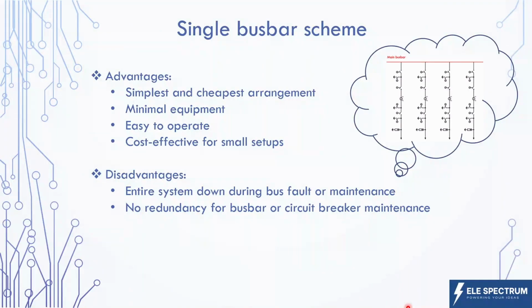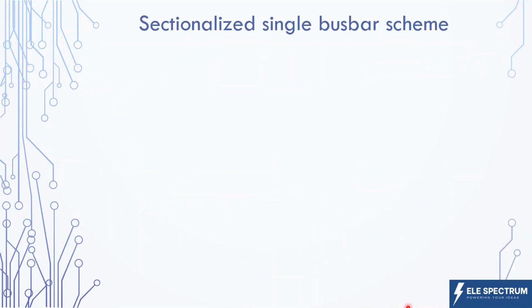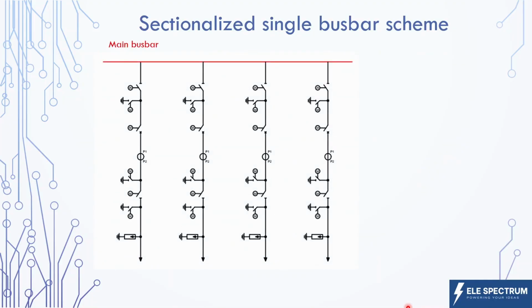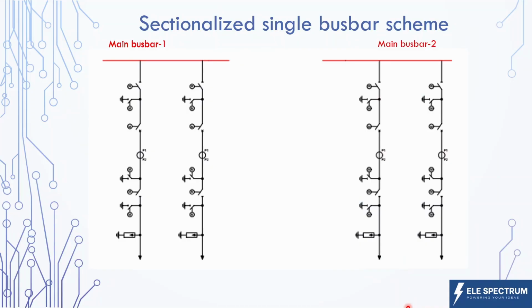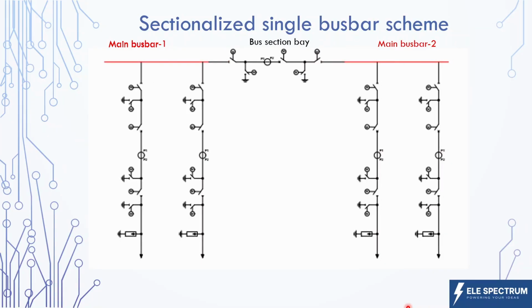If this is clear, then let's discuss the next bus bar scheme, that is sectionalized single bus bar scheme. Let's start from where we left off with the single bus bar scheme, and let's split this bus bar into two parts. So we have one section with one bus bar and another section with a second bus bar, and we can connect these two sections with a bus section bay, which consists of a circuit breaker, disconnector, earthing switch, and CTs. So this bus section bay simply connects two different sections of bus bars.